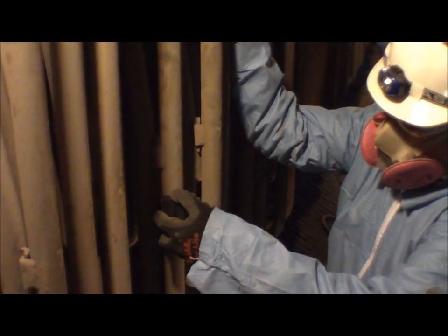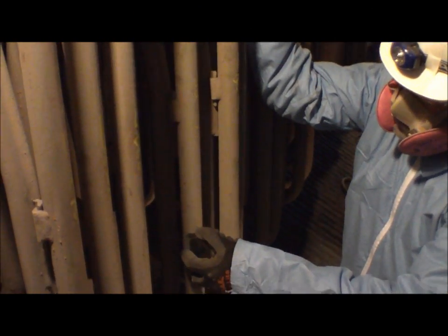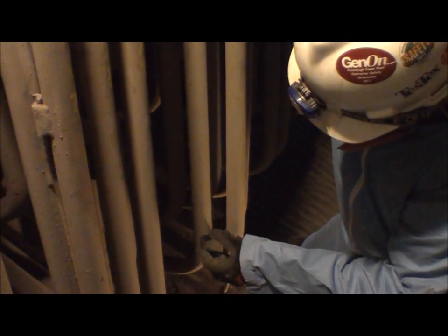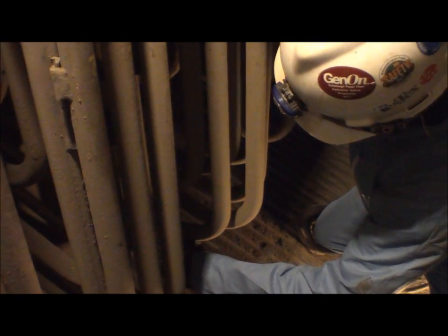Here's an up close of the scanner doing his job. He's starting above the bend, making sure he gets the bend and gets a little bit past each bend to make sure that there is no magnetite buildup. Again, if there was any indication of magnetite buildup, we would go ahead and re-pull the tube and mark it where the magnetite buildup started and where it ended.